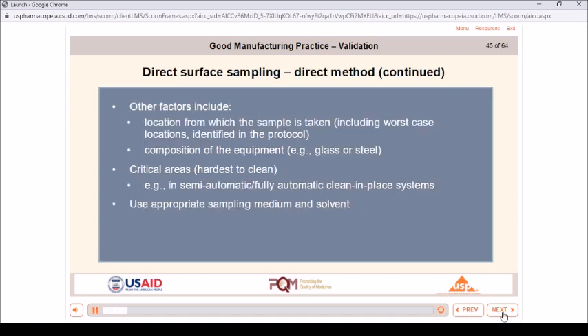Direct surface sampling, direct method, continued. Other factors include location from which the sample is taken, including worst-case locations identified in the protocol, composition of the equipment, e.g., glass or steel, critical areas, hardest to clean, e.g., in semi-automatic, fully automatic, clean-in-place systems. Use appropriate sampling medium and solvent.